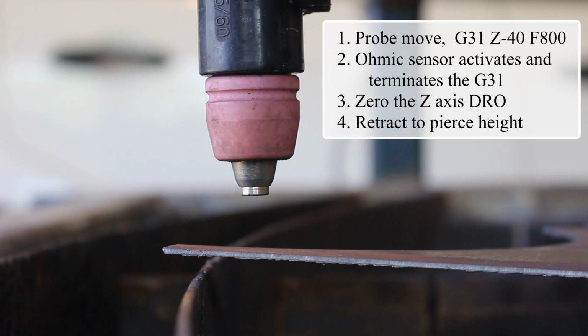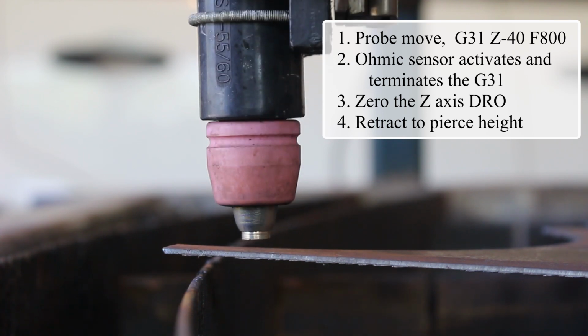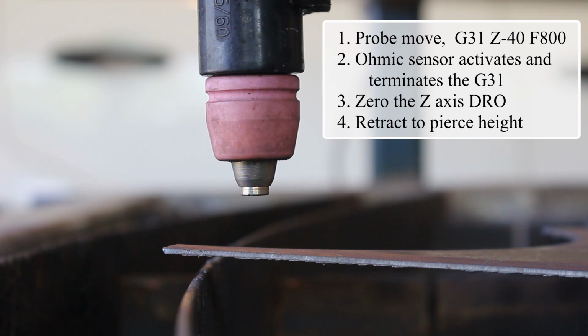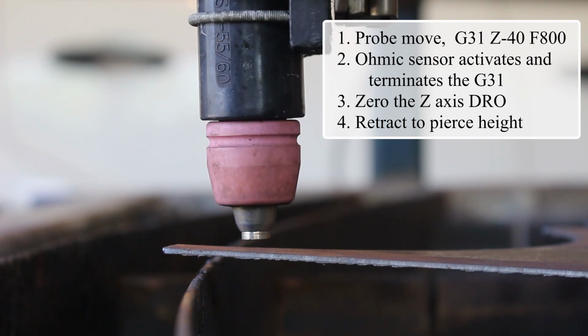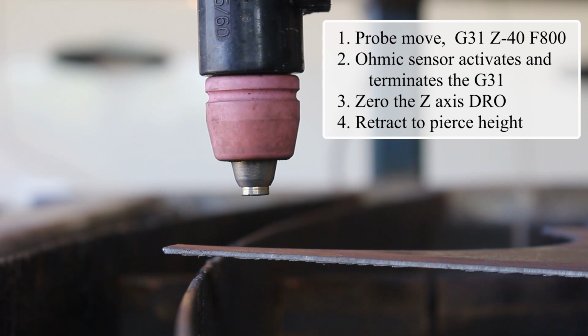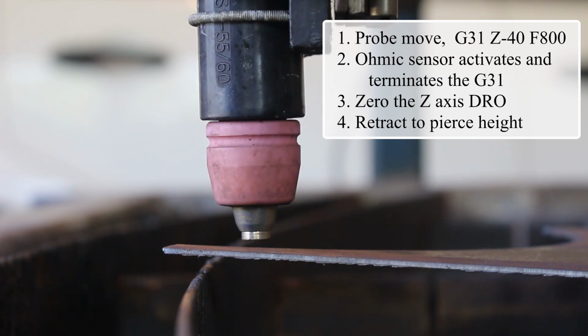So with the Ohmic sensor fitted up, here we are back at our thin example, and you can see that the material deflects very little and the torch ends up at an appropriate height to pierce the material. Now if for any reason the Ohmic sensor does not trigger the probe, then the floating head switch will activate it as per before. The macro can then work out which sensor triggered the probe input and either apply the offset for the floating head switch or not, as the case may be.